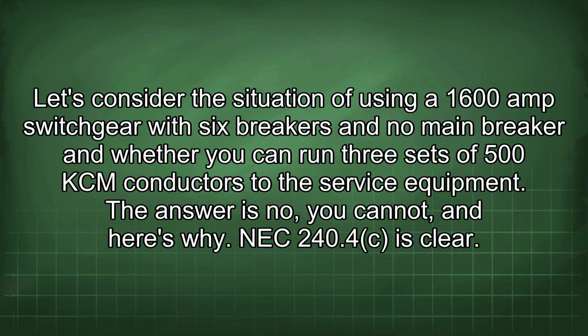Let's consider the situation of using a 1600 amp switchgear with 6 breakers and no main breaker, and whether you can run 3 sets of 500 kcm conductors to the service equipment. The answer is no, you cannot, and here's why.